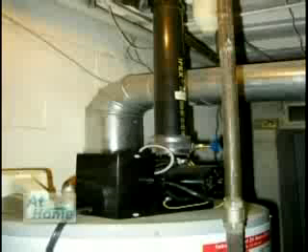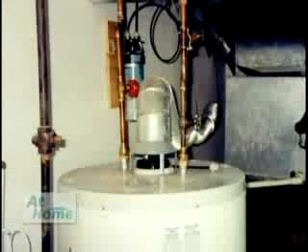All right, what is this? If you look at the very, very top, you'll see the pipe is disconnected. Now, this is a hot water tank, so the pipe is disconnected at the very top. So the exhaust pipe, the black exhaust pipe, and what's happening is the gases are actually entering back into the house. This is another hot water tank that has basically been altered, and if you notice, the exhaust simply goes into the open area behind the furnace in this case, so it's actually allowing gases into the house. Carbon monoxide is coming into these two homes. Okay, so these are renovations and alterations that people conduct and don't properly do.